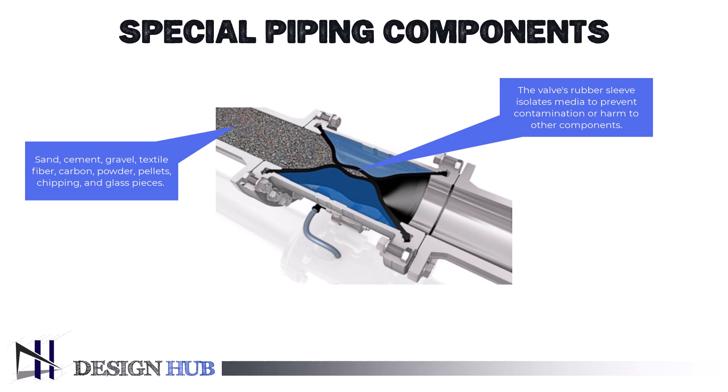Rubber hoses for air-operated pinch valves are typically pressed into place and centered by the socket covers of the housing ends. The valve shuts off as soon as pressured air enters the body — no additional actuator is needed. The force of the process flow causes the elastic rubber hose to begin to open when the air supply is cut off and the air volume exhausts. Sand, cement, gravel, textile fiber, carbon, powder, pellets, chipping, and glass pieces are examples of granular materials and slurries that work well with pinch valves.